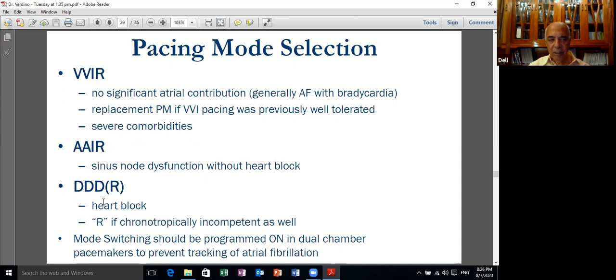chronotropically incompetent patients. Now we have mode switching, and this mode switching is whenever the atrial rate is accelerated, we stop tracking the atrium. So if the atrium went into atrial flutter, supraventricular tachycardia, or more commonly atrial fibrillation, we stop tracking the atrium. So we change from DDD into DDI, in which we do not track the atrium, not VVI, because if it is VVI, how does the pacemaker know that you went back to sinus rhythm? In VVI, there is no atrial electrode, so it cannot know that you went back to a sinus rhythm. That's why mode switching changes DDD into DDI rather than VVI.